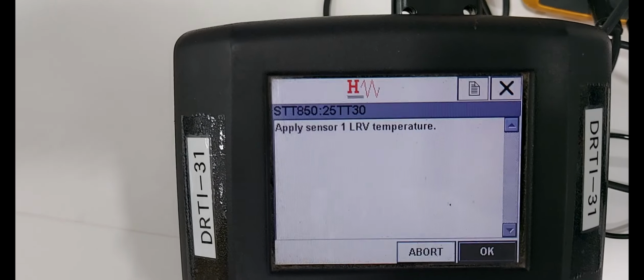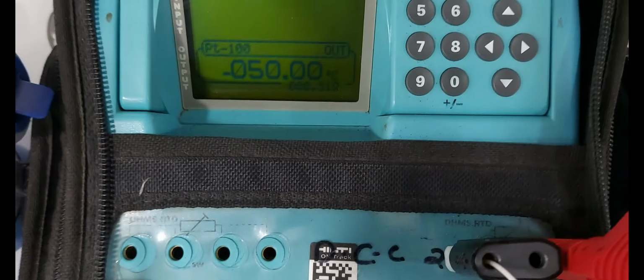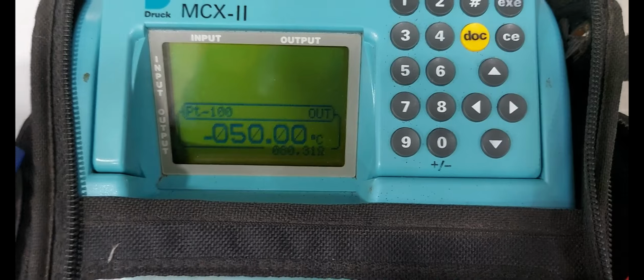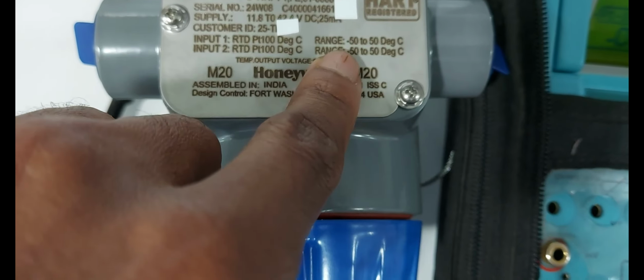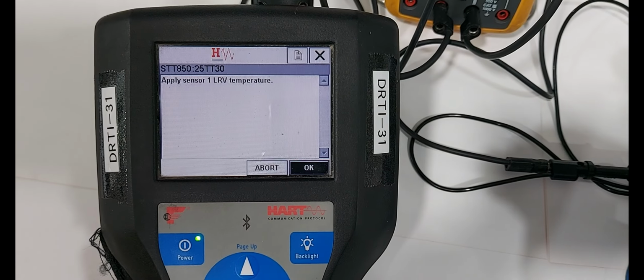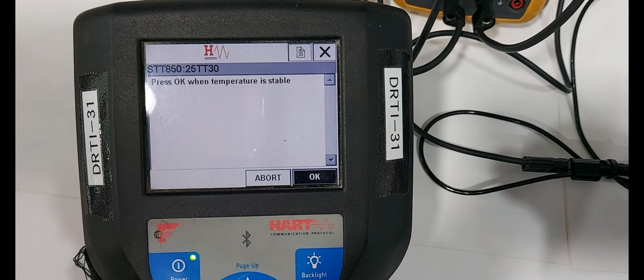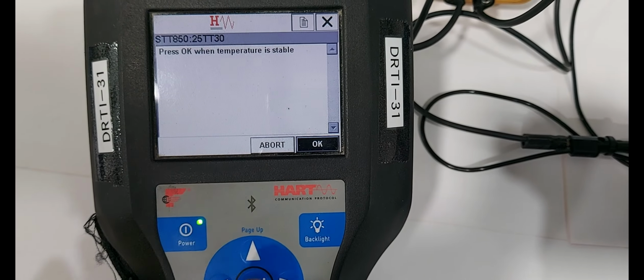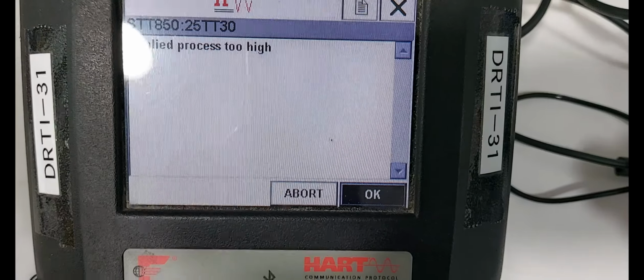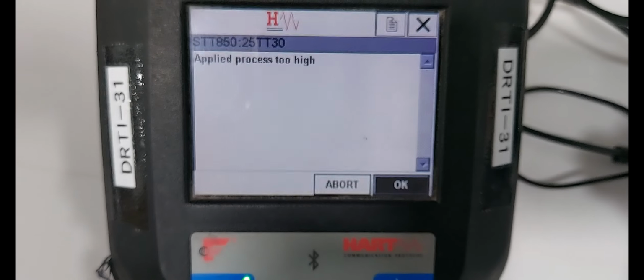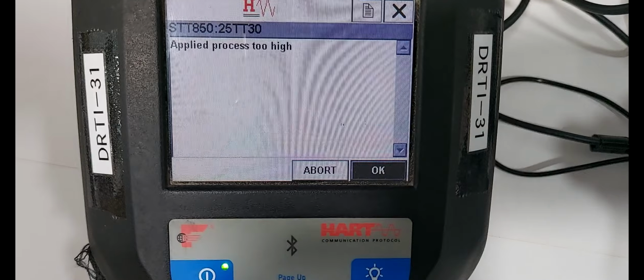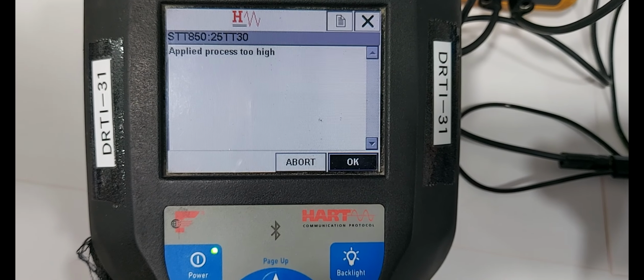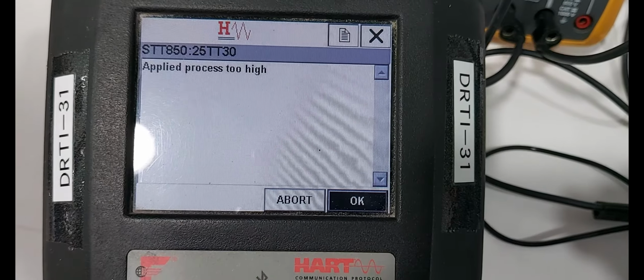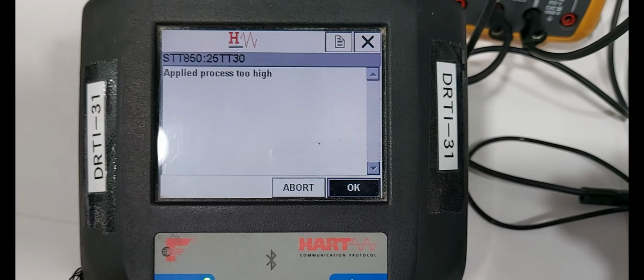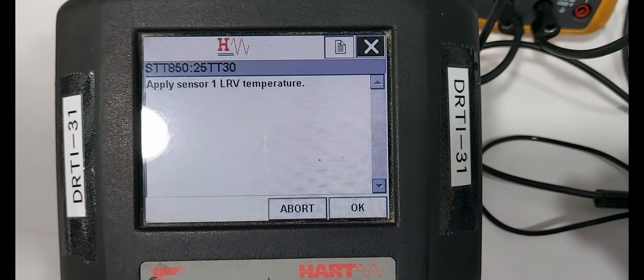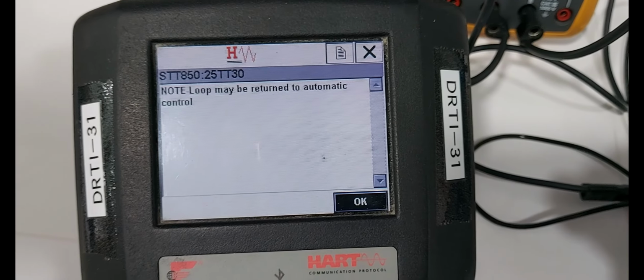Now sensor 1 LRV temperature. The multifunction calibrator is already applying minus 50 degrees, the LRV value. Transmitter lower value is minus 50 degrees. Then press OK. Wait until the temperature is stable. Now the temperature is stable, then press OK. Now the transmitter is getting one alarm: applied process value too high. Next we are changing the alarm mode. This is the alarm removing procedure. Then press OK. Abort. Then press OK. Back.